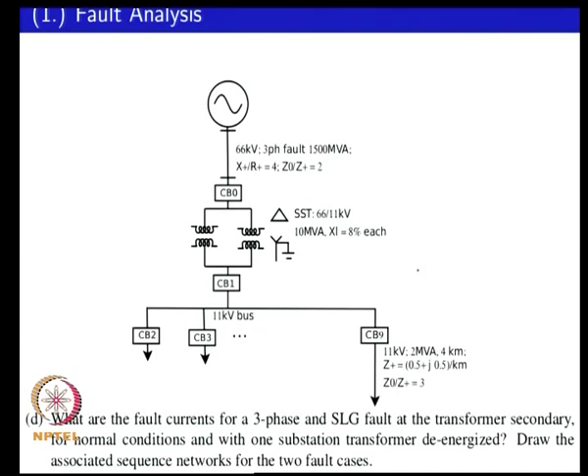The next question is: what are the fault current levels for three-phase and single line-to-ground faults at the transformer secondary — which we just calculated — and then what happens for faults at the 2-kilometer and 4-kilometer points on the feeder? The procedure for doing this is similar to what we did for the transformer secondary fault. You will have the additional impedances of the remaining sections to include, and repeat it for both the one-transformer and two-transformer cases.